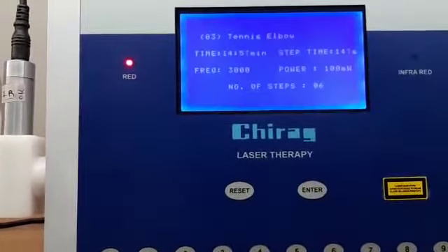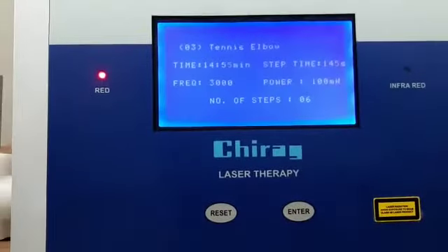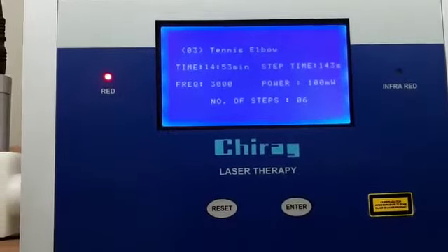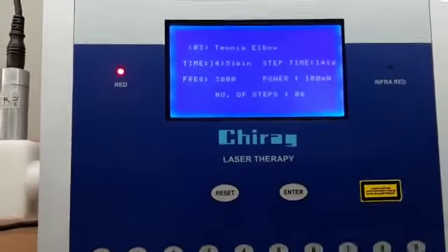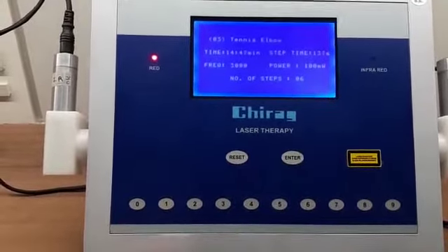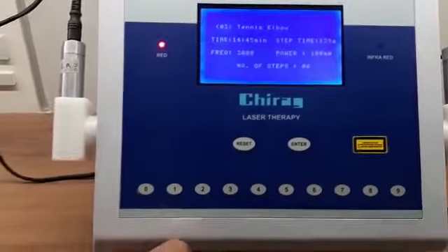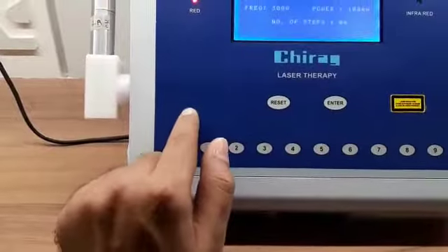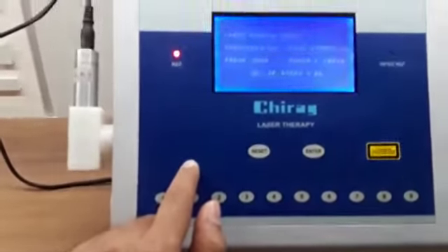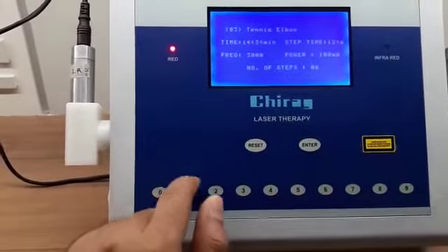The preset program has a frequency of 3000 Hz, power of 100 milliwatts, and number of steps is 6. Number of steps is the number of parts into which the area is divided. For example, if we are taking an elbow, this elbow portion can be divided into 6 steps. In these 6 steps, we can divide the total treatment area.